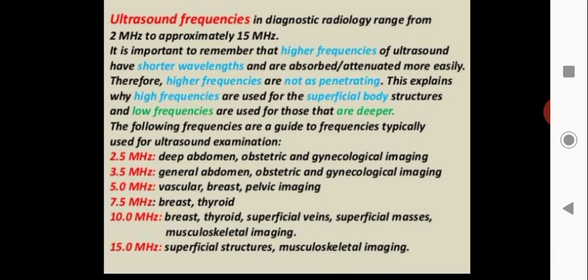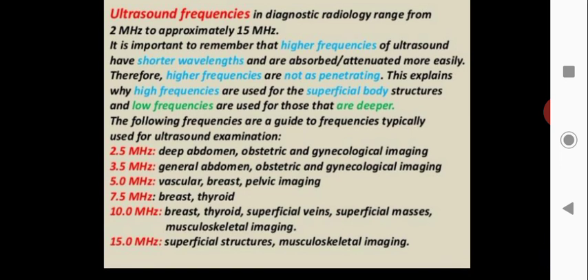Higher frequency ultrasounds have shorter wavelengths and are absorbed more easily, therefore higher frequencies are not as penetrating. This explains why higher frequencies are used for superficial body structures and lower frequencies are used for deeper structures. Frequencies typically used for ultrasonic examination include 2.5, 3.5, 7.5, and 10 MHz.